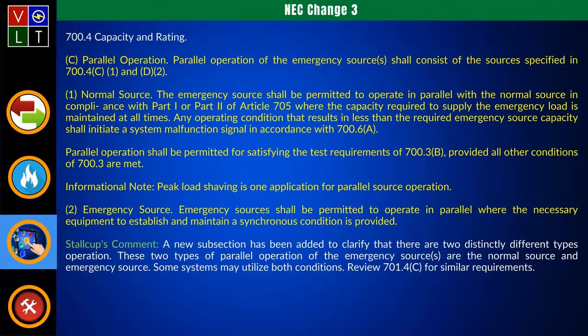We give you an example here, and in our illustrations we lay this out to let you understand the difference between a normal source and emergency source. Because when you get into emergency source, they tell you it's permitted to operate in parallel where necessary equipment is used to establish and maintain what? A synchronous condition. Right. Where a normal source is not like that.